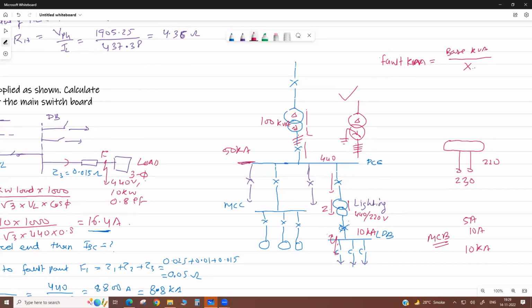So suppose 100 kVA, and suppose the fault occurs at the LT bushing here, at the PCC bus. Then only the impedance of this transformer, the reactance of this transformer, is there. Suppose it is 10%. If the fault occurs here, then only the impedance of the transformer will take care. So suppose it is 10%, the base kVA is 100, we assume. Then divide by 10%, so it is multiplied by 10. It becomes 1000 kVA. It means in the normal case your power capacity of the transformer is 100 kVA, but in this case it becomes 1000 kVA.